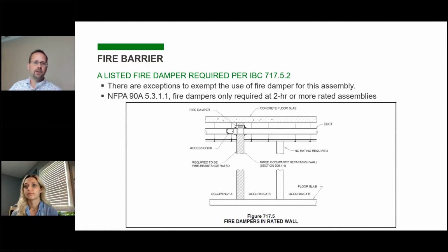Now, as far as general fire barriers surrounding individual rooms, there are still some differences in code and quite a few exceptions that can be confusing, and there are differences in interpretation that we found as we've done work around the country. Number one, NFPA does not require any dampers in a 1 hour or less fire barrier, with no caveats or suggestions. So that's the biggest difference between the NFPA and the IBC from this standpoint.